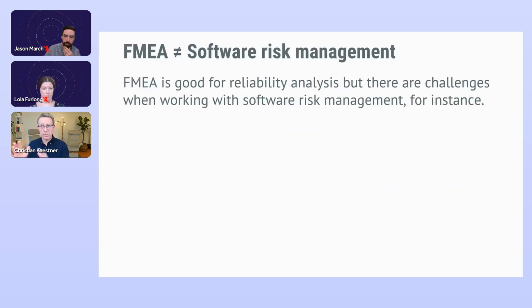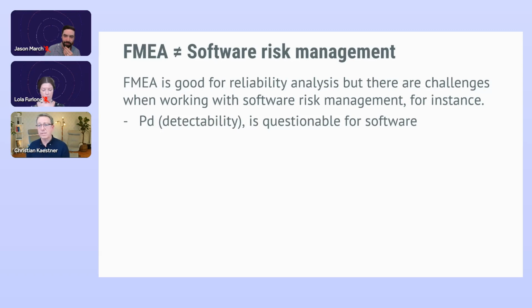I might disappoint whoever asked this question, because I think FMEA is not software risk management, in my opinion. One reason is that when working with an FMEA, you should have probability of detection, or detectability, and that might be questionable with software, because software failure is often very unexpected and comes without warnings. So when a failure is detected in software, it's often too late. You don't get any pre-warnings at all. In other products, detectability might be very useful because you can listen, you can hear, you can notice that something is going wrong. With software, when you see the blue screen, well, you're lost.